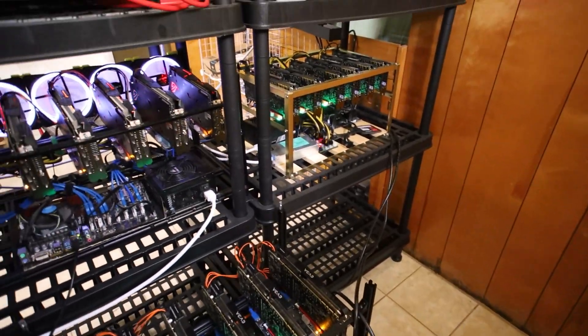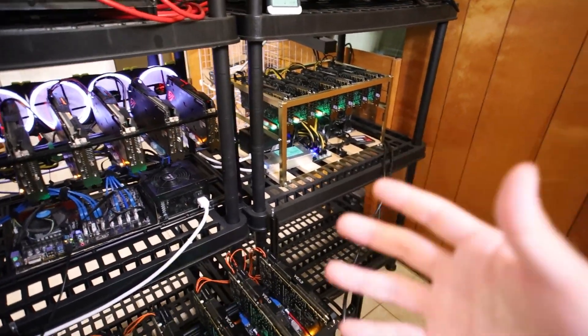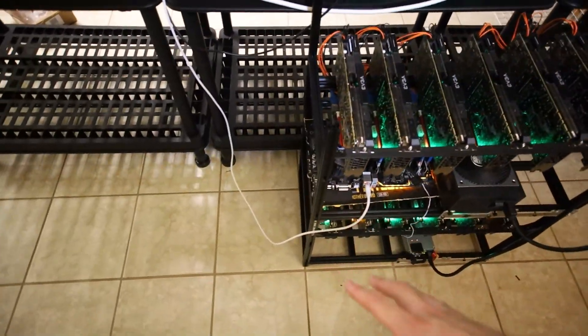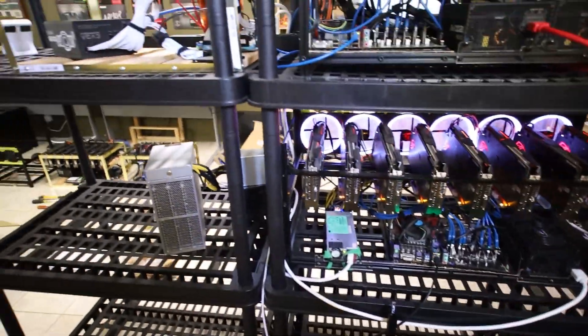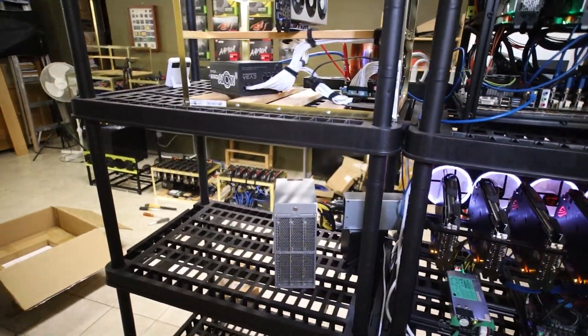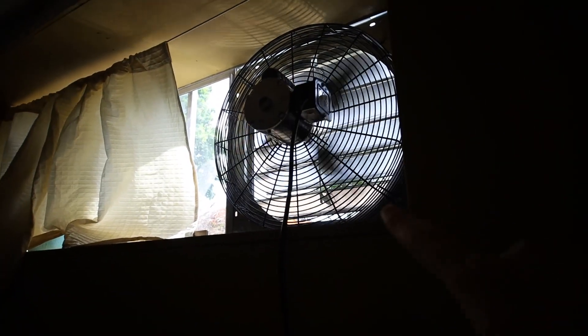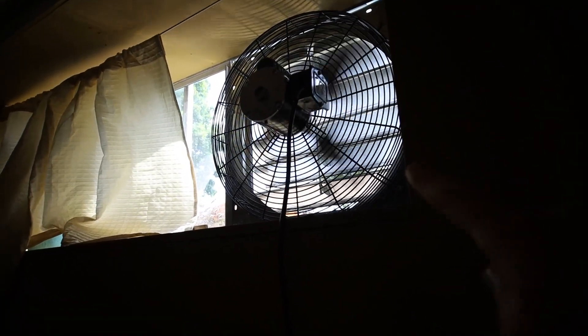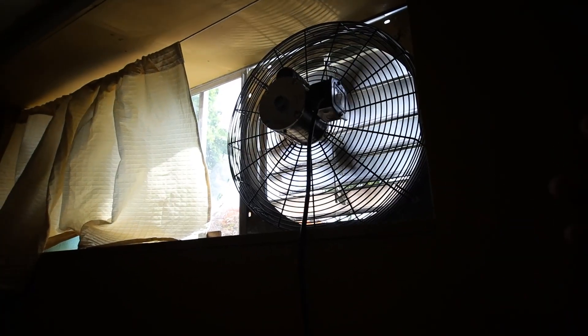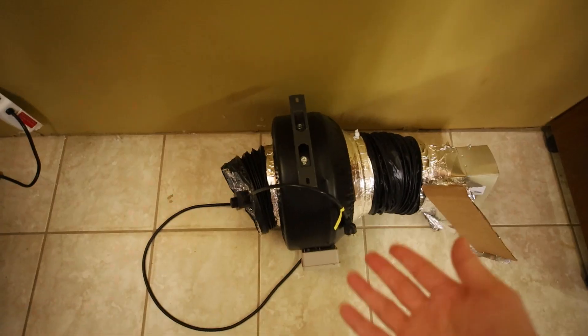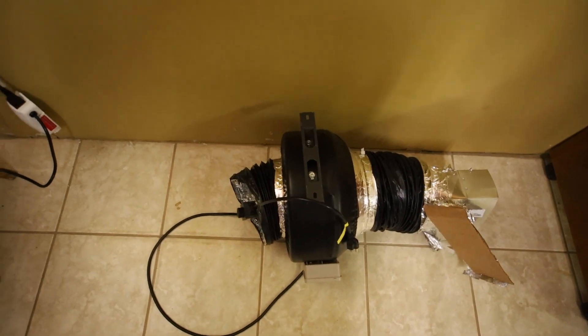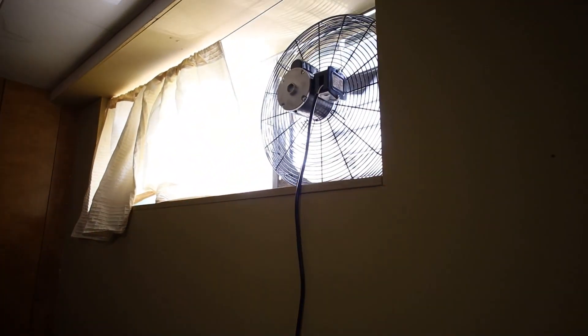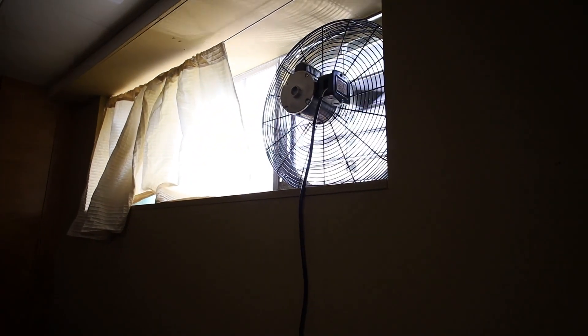And it definitely feels a lot cooler in this area here. It definitely felt a lot more warmer, hot spots especially like over here and where I'm standing. But basically now that we have 2000 CFM coming out of this 18 inch exhaust fan, way better. We're essentially getting double the CFM than the 8 inch inline fan that I had here. So wow, that makes a world of a difference.